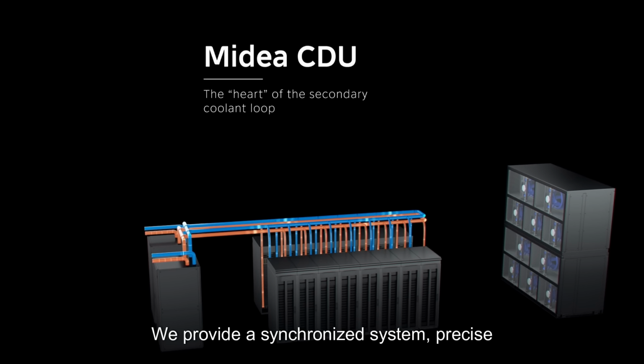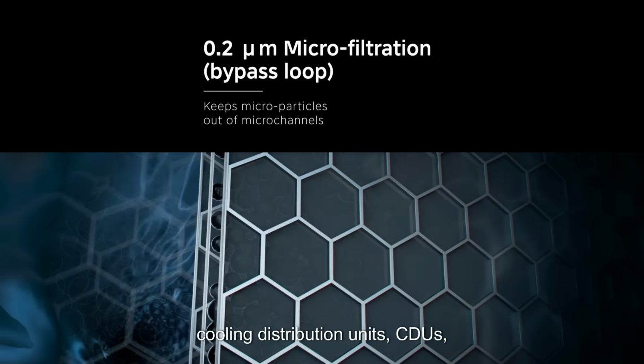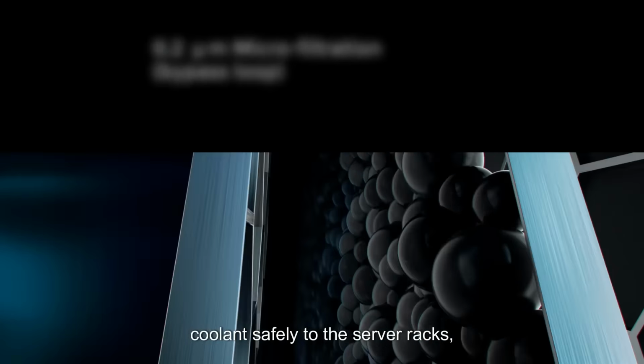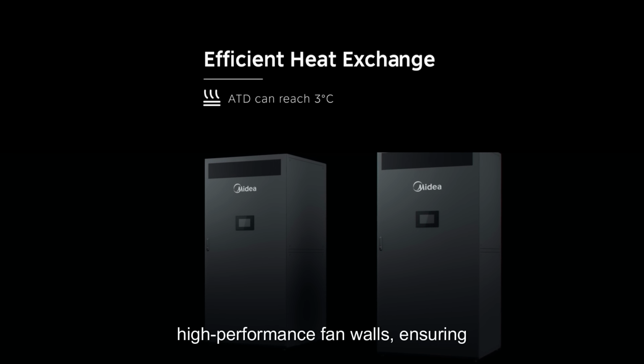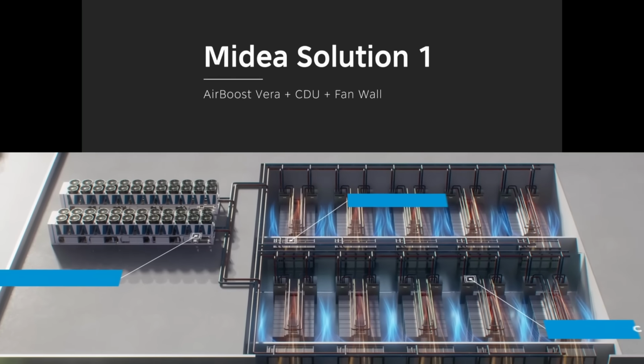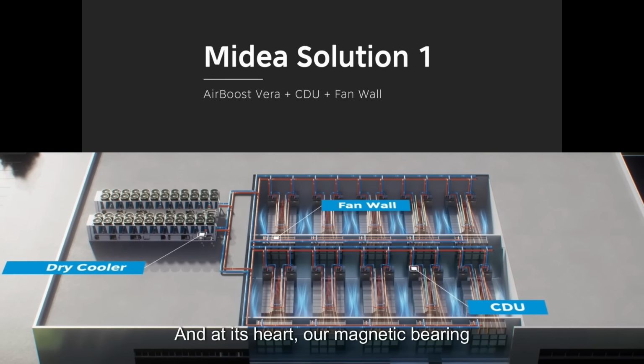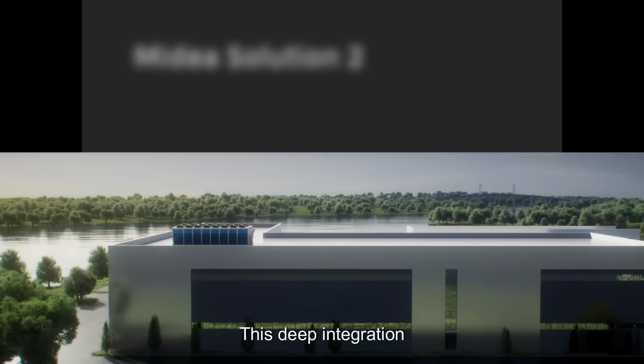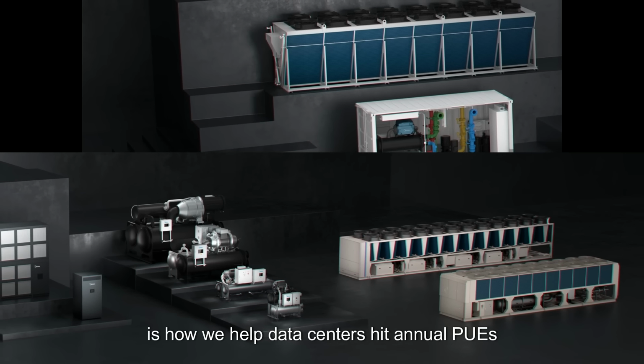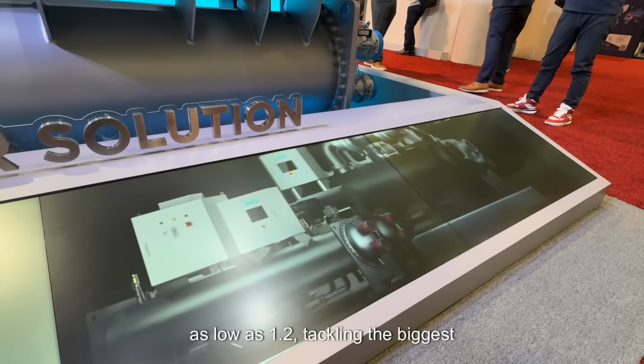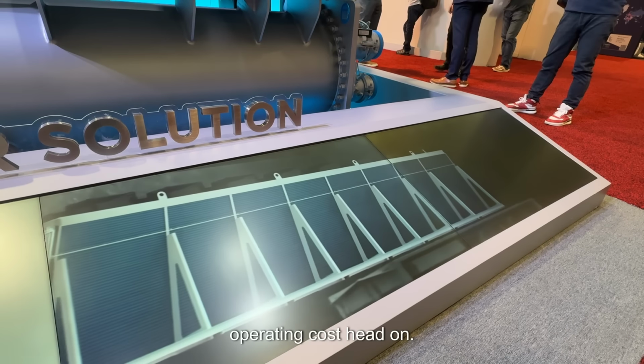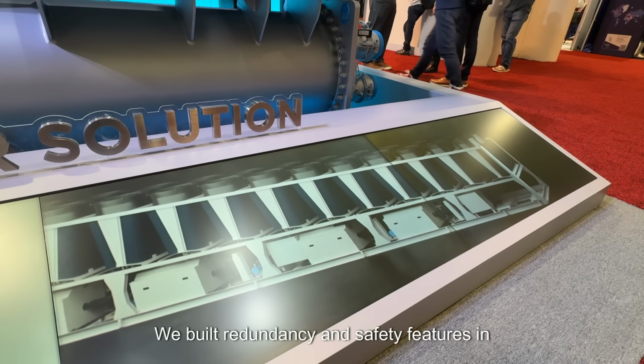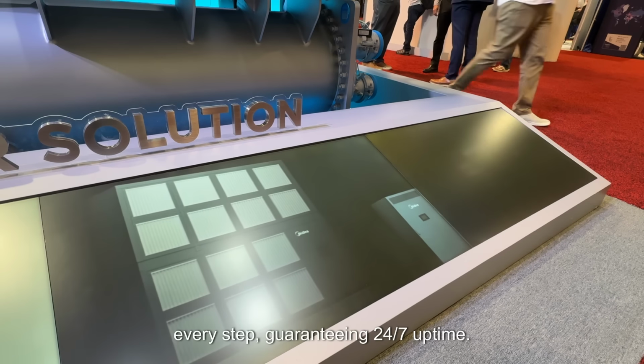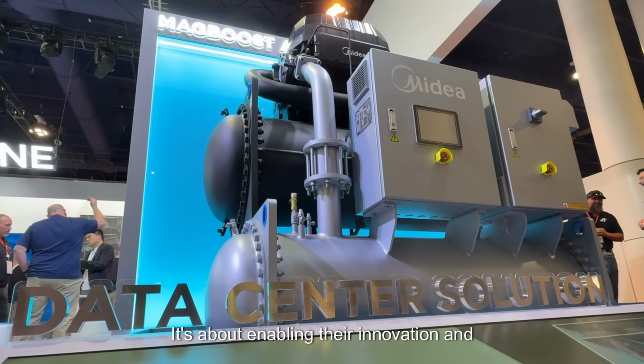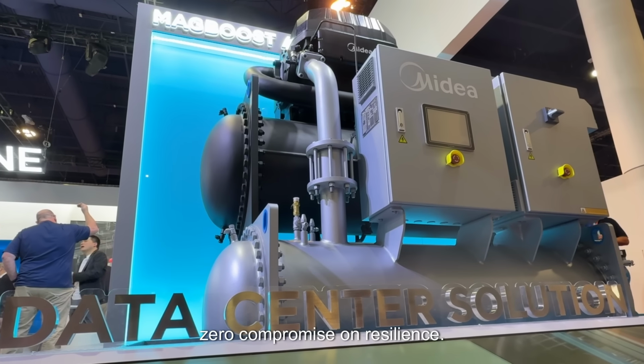That's where our integrated approach stands out. We provide a synchronized system: precise cooling distribution units, or CDUs, delivering coolant safely to the server racks, high-performance fan walls ensuring perfect airflow management in the room, and at its heart, our magnetic bearing chiller supplies cooling with ultra-high part load efficiency. This deep integration is how we help data centers hit annual PUEs as low as 1.2, tackling the biggest operating cost head on. We built redundancy and safety features into every step, guaranteeing 24/7 uptime. It's about enabling their innovation with zero compromise on resilience.